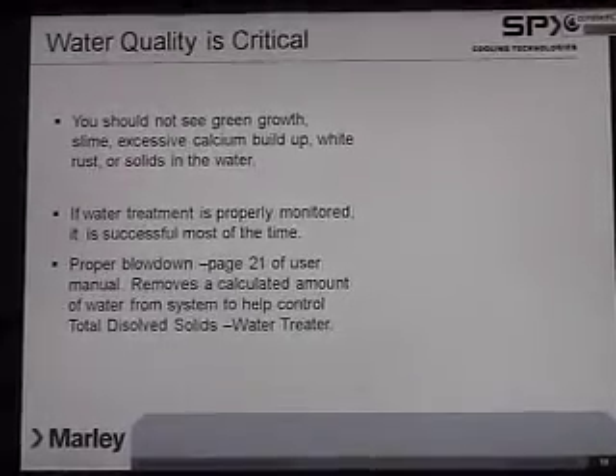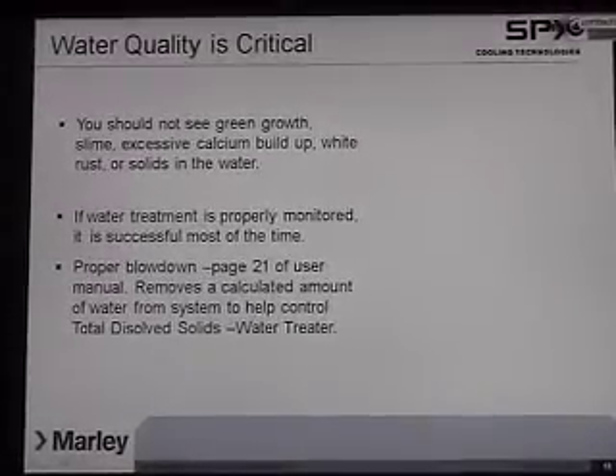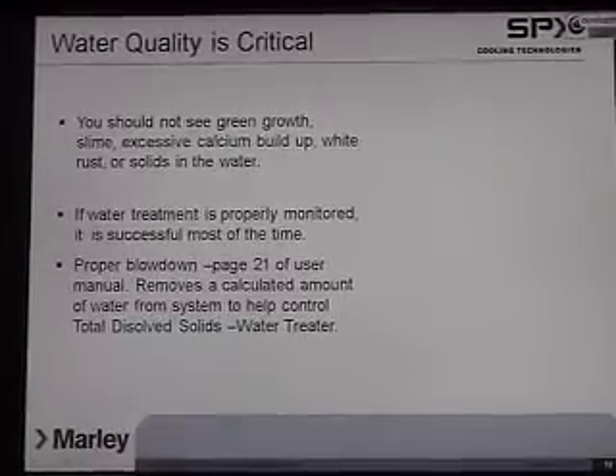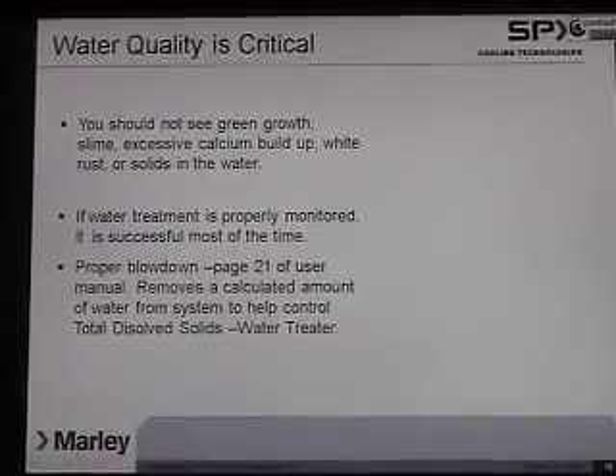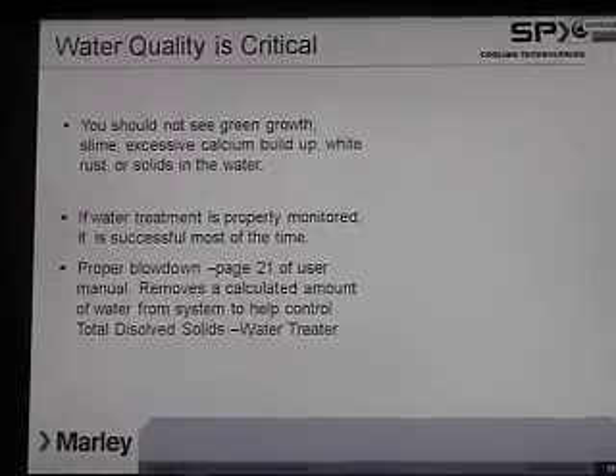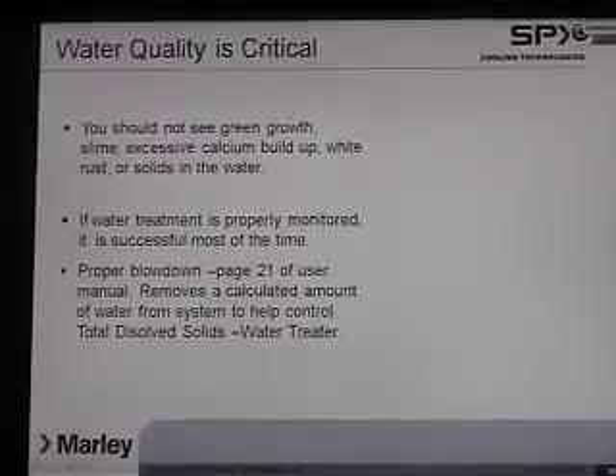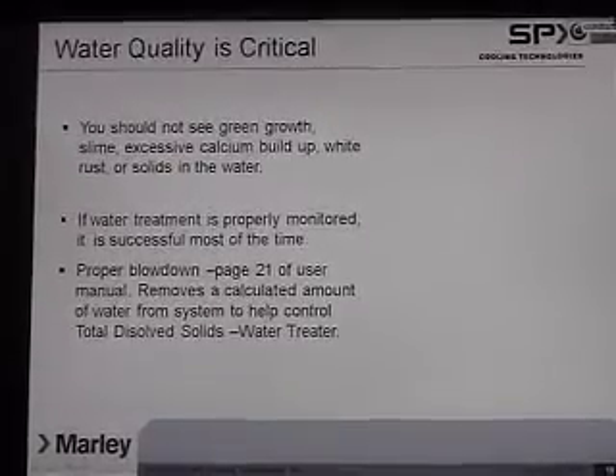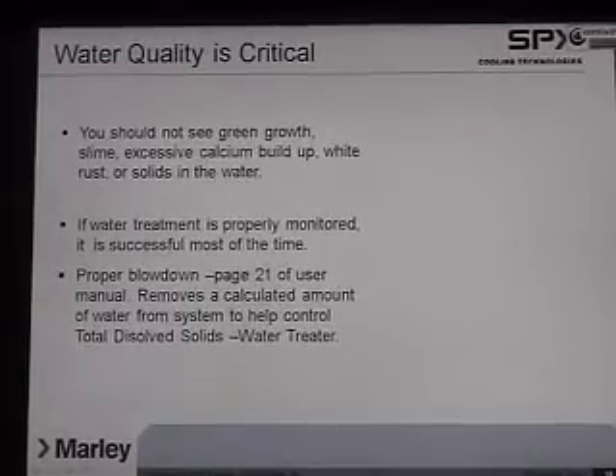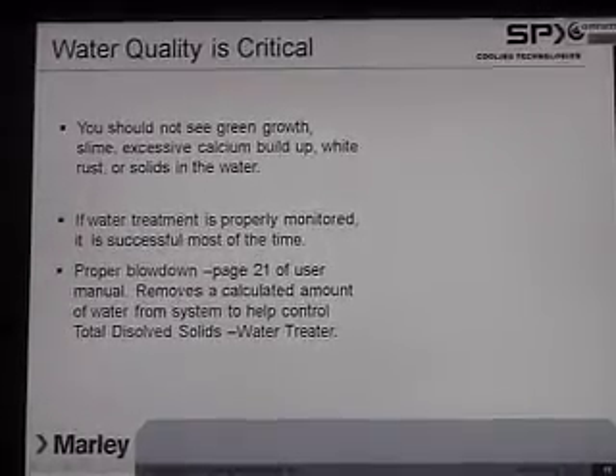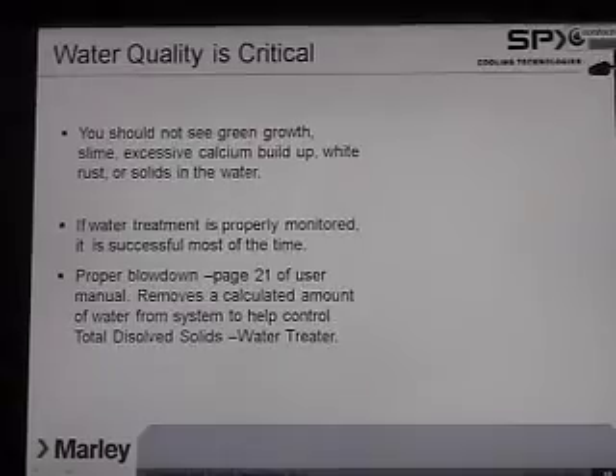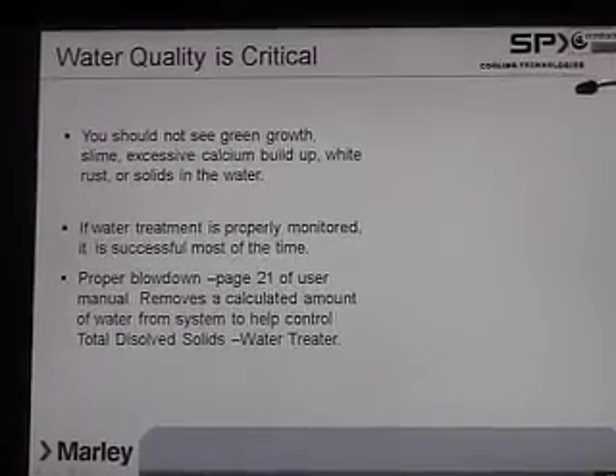The number one way to take care of your cooling tower is professional water treatment. One, it will help prevent Legionella, and two, it will help your cooling tower fill last longer because you won't get scale built up in your cooling tower. So my number one recommendation is professional water treatment.